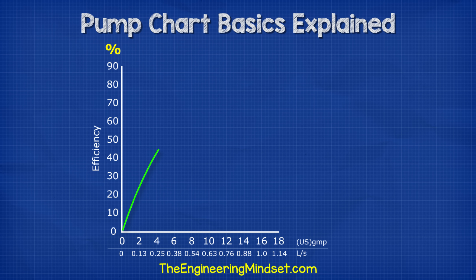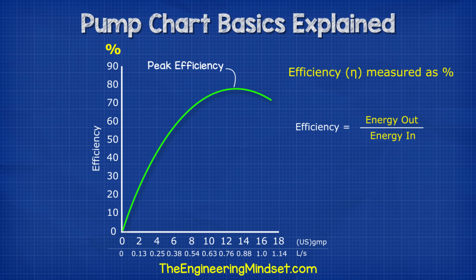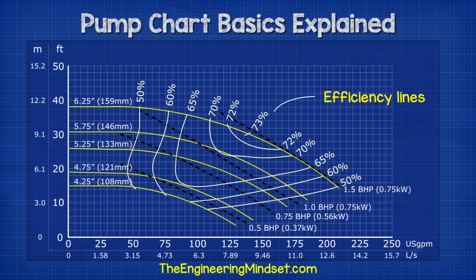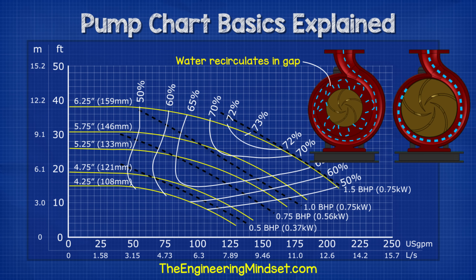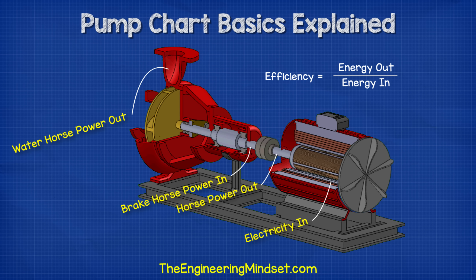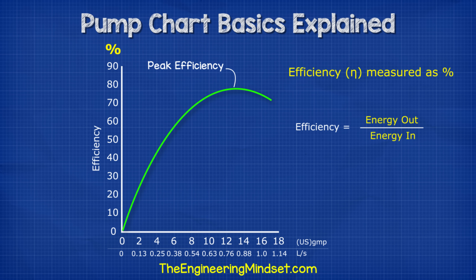Efficiency. Some charts will display the efficiency curve of the pump, measured in percent. We will usually see this curved line where the pump increases up to its maximum efficiency and then it starts to decline again. Charts that display different impeller sizes will usually have efficiency displayed in more complex plot lines, where each line displays the percentage of efficiency. In both charts, you can see that the efficiency varies depending on how you operate the pump. In multiple impeller size charts, we see that the efficiency decreases as the impeller size also decreases, and that's because the gap between the impeller and the pump casing increases, which will allow water to recirculate in this region and therefore waste energy. The efficiency is the ratio between the amount of energy going into the pump versus the amount of energy we get out of the pump, so ideally we want this to be as close as possible to the peak for optimal performance.